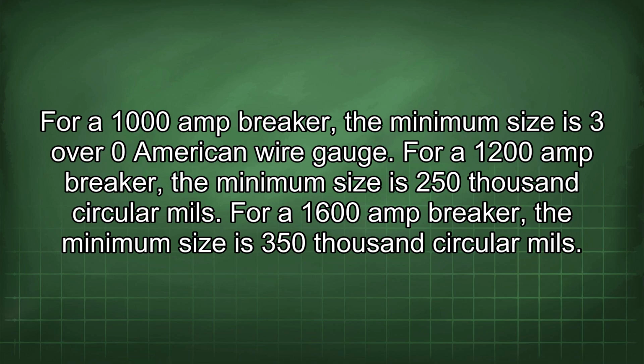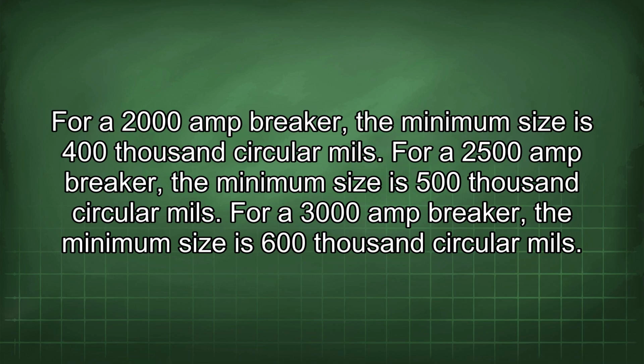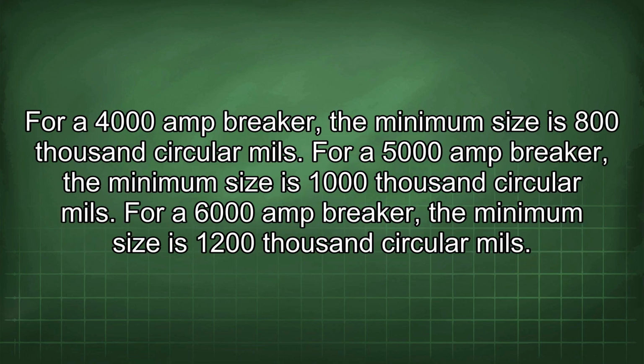For a 1600 amp breaker, the minimum size is 350,000 circular mils. For a 2000 amp breaker, the minimum size is 400,000 circular mils. For a 2500 amp breaker, the minimum size is 500,000 circular mils. For a 3000 amp breaker, the minimum size is 600,000 circular mils. For a 4000 amp breaker, the minimum size is 800,000 circular mils. For a 5000 amp breaker, the minimum size is 1,000,000 circular mils. For a 6000 amp breaker, the minimum size is 1,200,000 circular mils.